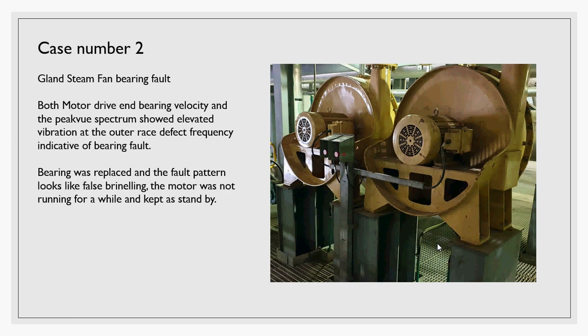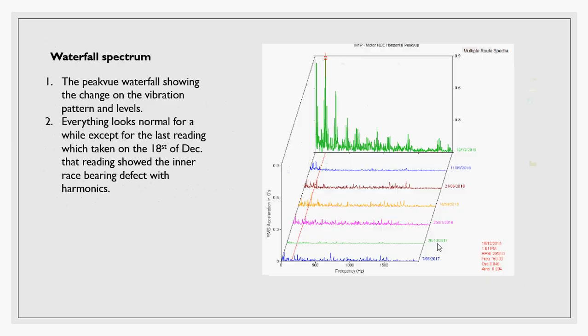The motor was running for a while and then kept on standby, and because it was on standby for a while, that was the main reason the vibration kept being transmitted from the running machine to the standby one. One solution is to isolate the two machines — put some mounts or dampers — to stop the transmitted vibration from the running machine to the standby one.